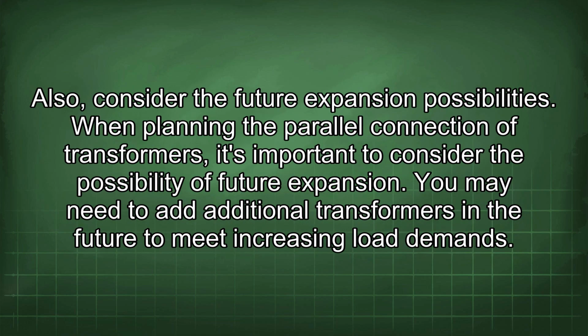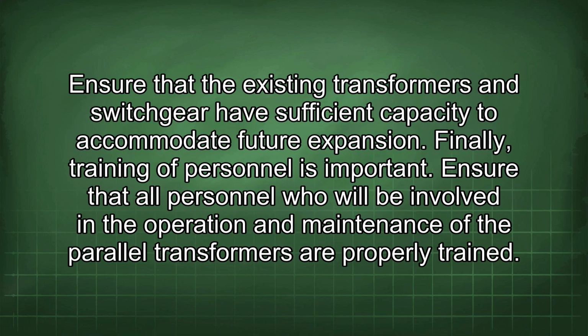Also, consider the future expansion possibilities. When planning the parallel connection of transformers, it's important to consider the possibility of future expansion. You may need to add additional transformers in the future to meet increasing load demands. Ensure that the existing transformers and switchgear have sufficient capacity to accommodate future expansion.